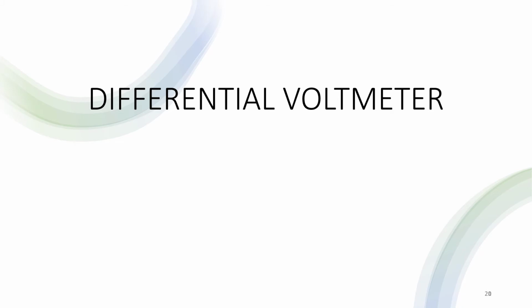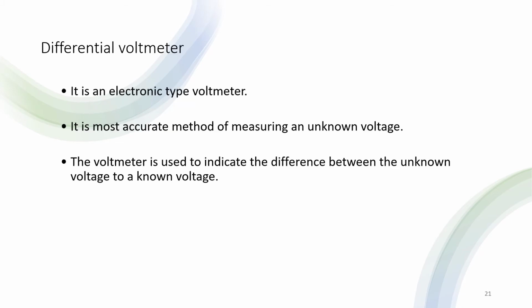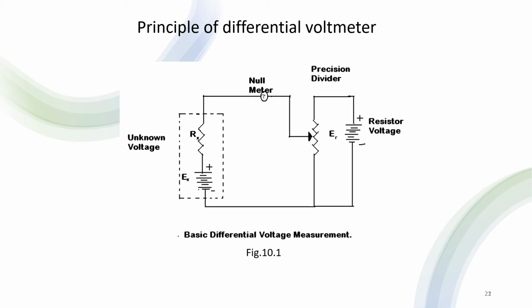Differential voltmeter. A differential voltmeter works on the principle of comparison of unknown voltage with known voltage. This is one of the most common and accurate methods of measuring unknown voltages. In this technique, the voltmeter is used to indicate the difference between a known voltage and an unknown voltage. That is, an unknown voltage is compared to a known voltage. The basic differential voltmeter is as shown in this figure. It uses a null indicator which is connected between the known voltage and the unknown voltage through a potentiometer.